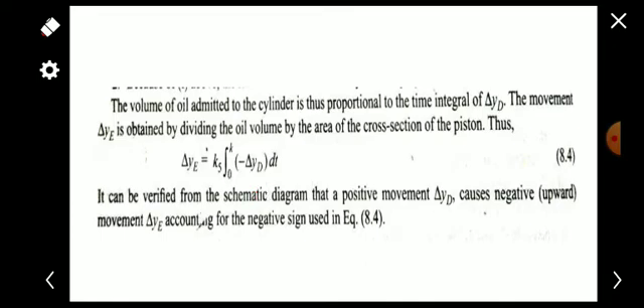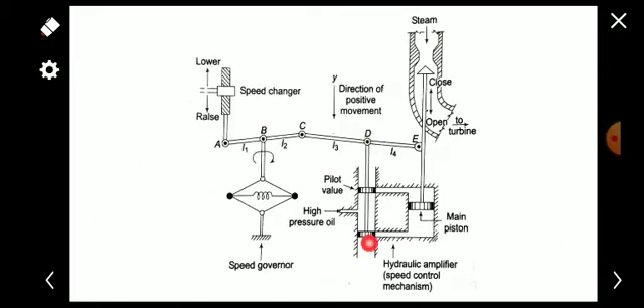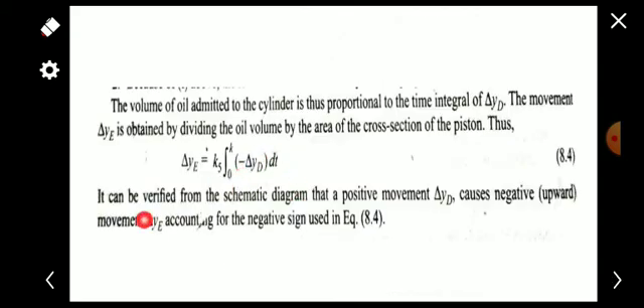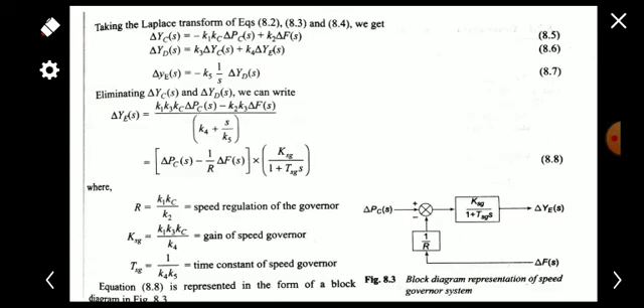The integral of delta_yd gives the change in delta_ye. If point D moves downwards (positive delta_yd), the high pressure oil comes to the piston through this path and the main piston moves upward — that is, delta_ye moves upward. Hence the negative sign is verified: a positive movement delta_yd causes a negative movement delta_ye, as can be confirmed from the schematic diagram.